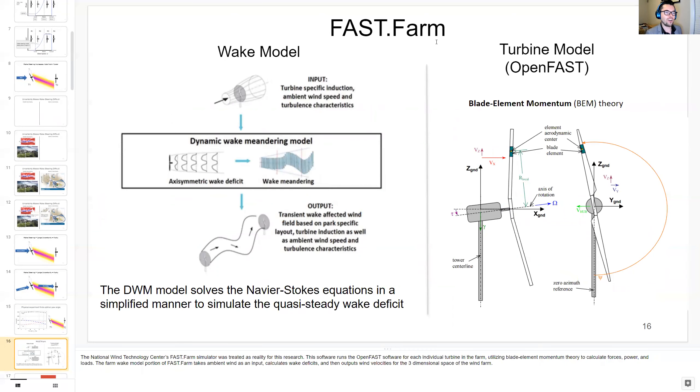I used the FAST.Farm wake simulator, wind farm simulator, as developed by the National Wind Technology Center. And this software runs the OpenFAST software for each individual turbine in the farm using blade element momentum to calculate forces, power, and loads. And then the farm wake model portion of FAST.Farm takes ambient wind as an input, and then it calculates wake deficits, and then outputs wind velocities for the three-dimensional space of the wind farm.